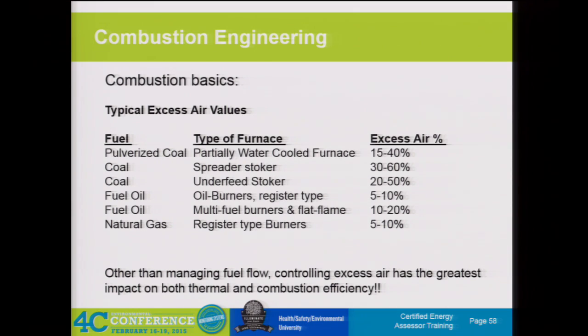These units that burn coal are heavily regulated and have limits on how much particulate matter, CO, and other contaminants are produced—because they're inherently less efficient, there's more carryover of pollutants, and it's a more difficult process to manage. Natural gas and fuel oil are much cleaner burning fuels and easier to manage the combustion. Therefore, they're inherently lower polluting. Managing the excess air is the biggest thermal combustion efficiency impact, and that's why the tune-up is required once a year. The rule requires coming back and calibrating and looking at this relationship in the unit and making those adjustments to improve efficiency.